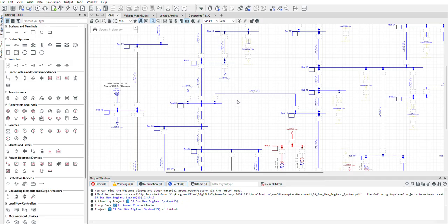But if you have a fault, for example, a short circuit here, the impedance will change and reduce a lot. So the distance relay realizes that we have a short circuit in this line. Or if we have a fault elsewhere in this line, again the impedance seen by this distance relay will change. The distance relay uses the impedance seen from that point, and, as a simple method, impedance is voltage divided by current, so V divided by I. So for a distance relay, we need both PT and CT.